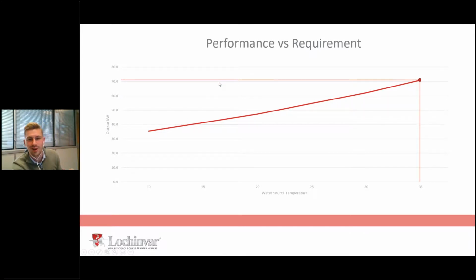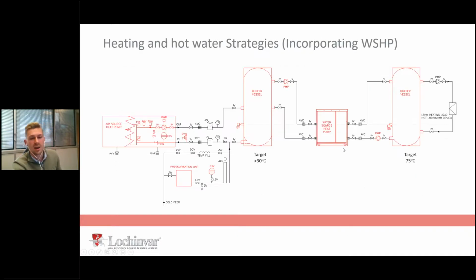So by doubling our output, our new efficiency, we're flowing at 70 degrees, bear in mind, which is a pretty high number. So flowing at 70 degrees with a source temperature of 35, this water source heat pump will now be 70 kilowatts and it'll be producing efficiencies of 540%. That's a very big statement. That's quite an impressive achievement. Sorry, I should say achievement rather than statement. It's an impressive achievement. And the way you do that, there's a few ways. We'll look at a few ways.